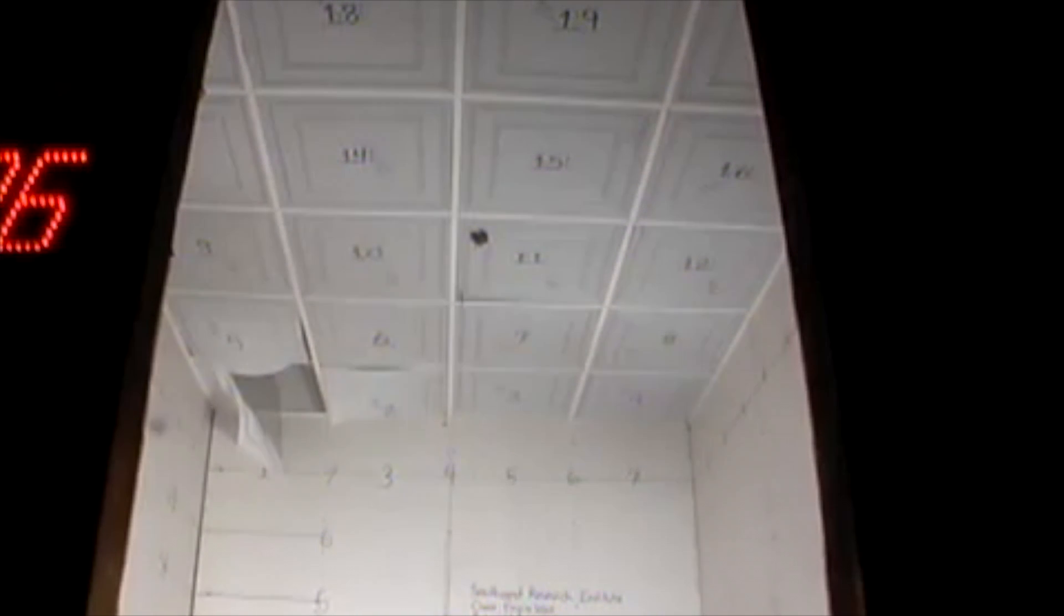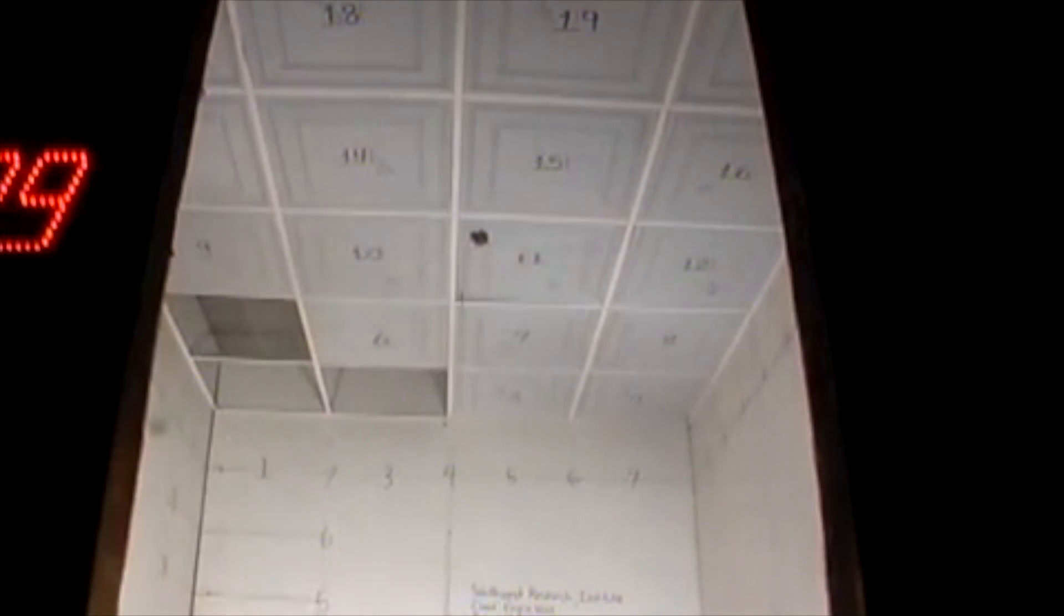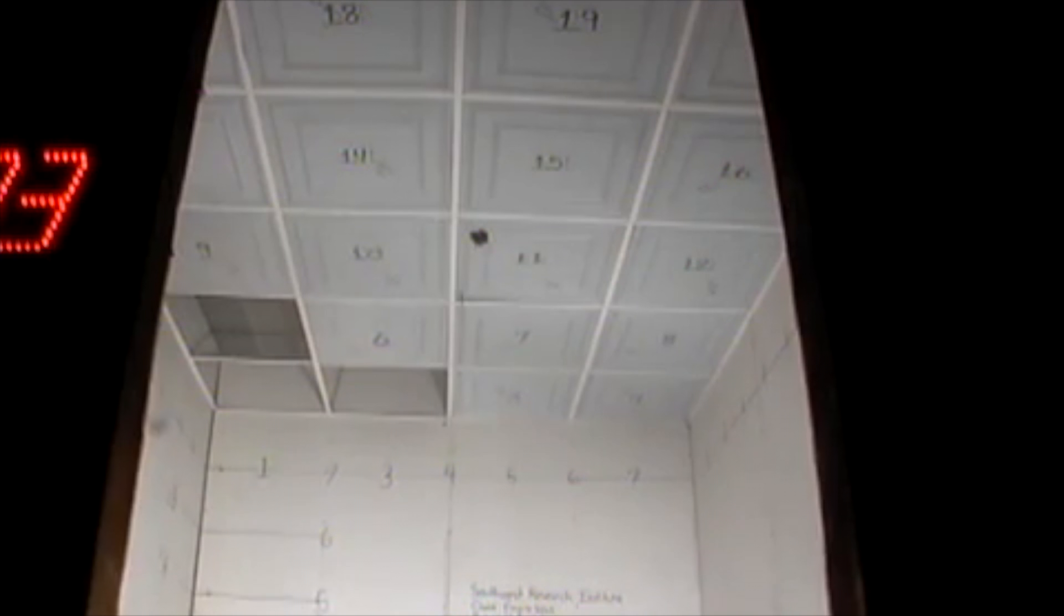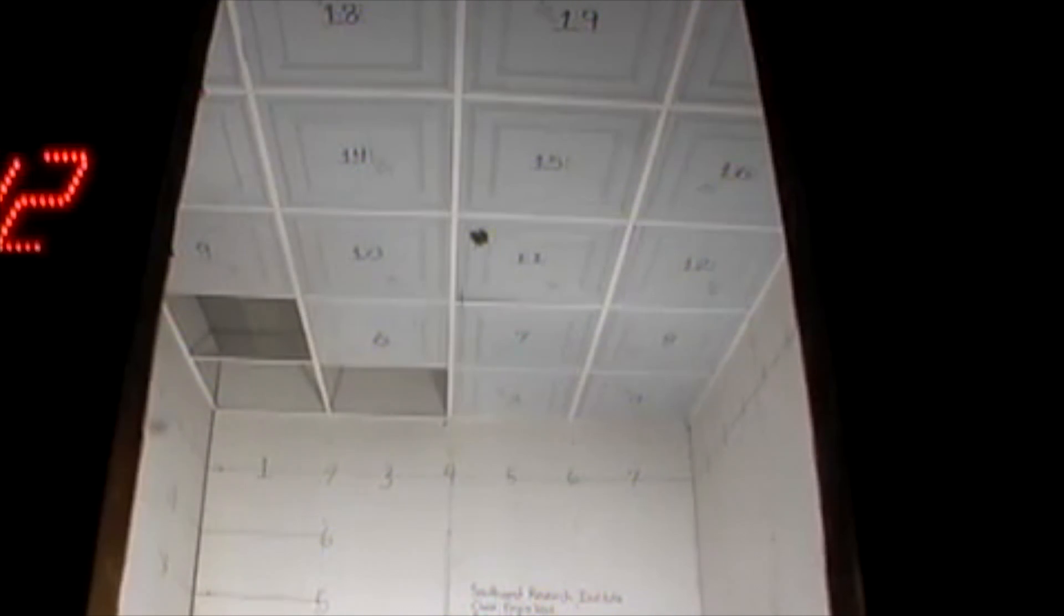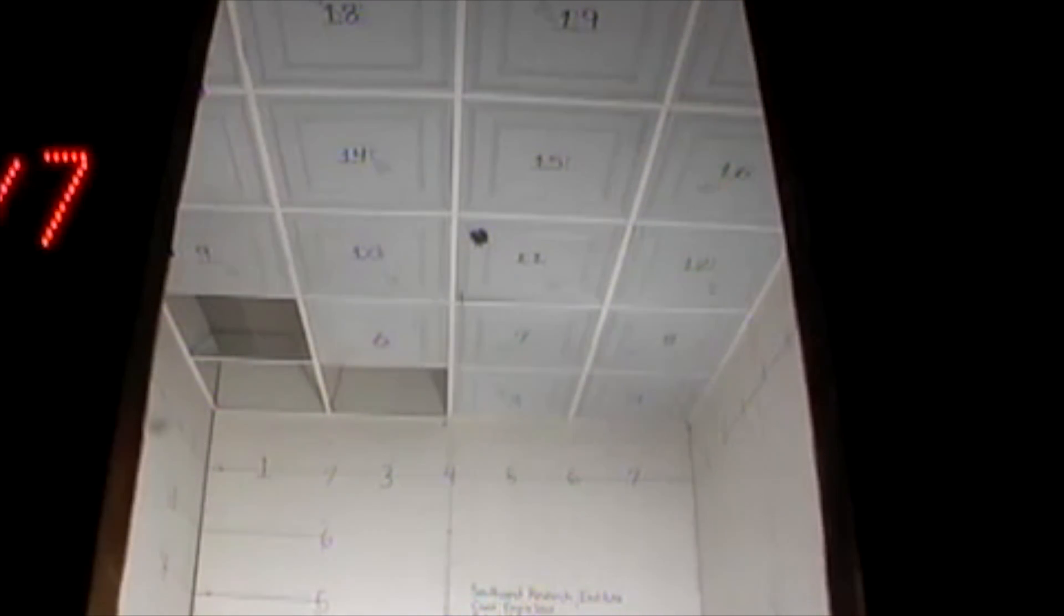Thermocouples are strategically positioned per the test standard to record temperatures at the grid, sprinkler, ceiling, and other levels. In actual use, the sprinklers would activate at their designated temperature, which is hotter than the temperature at which the panels drop out.